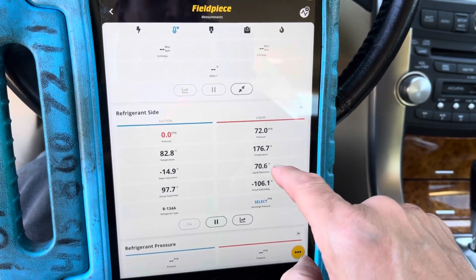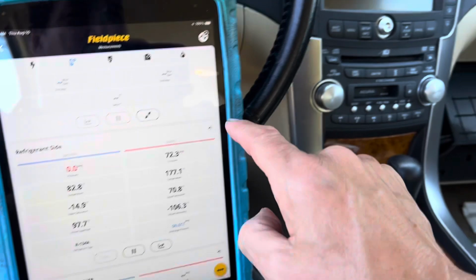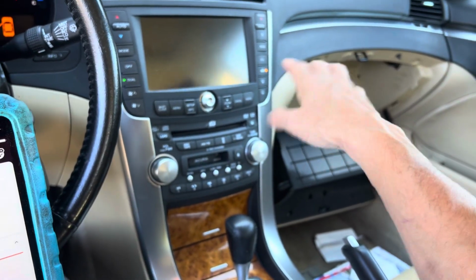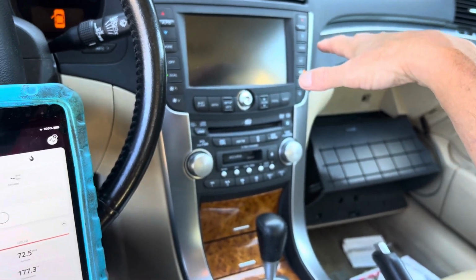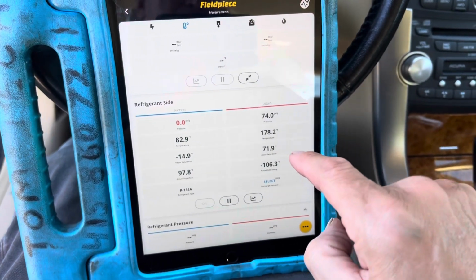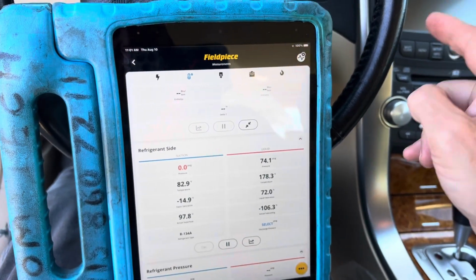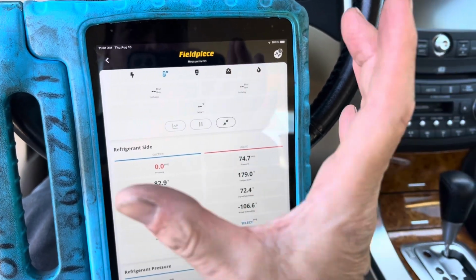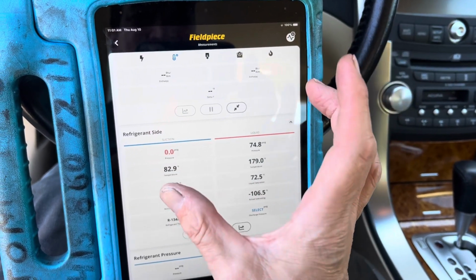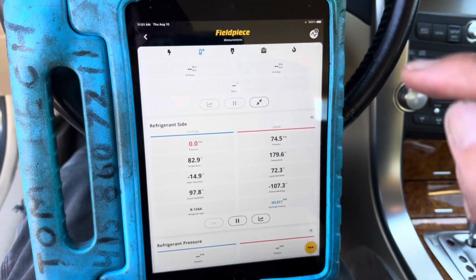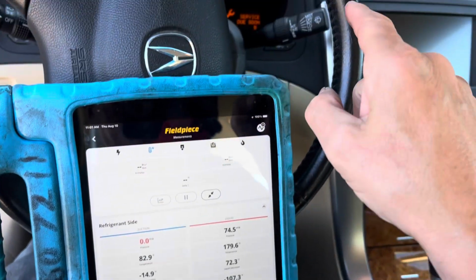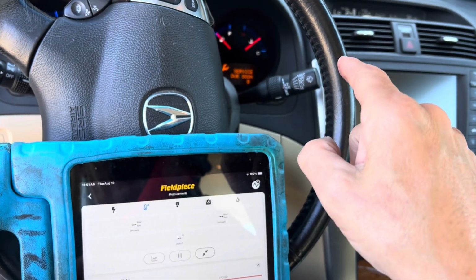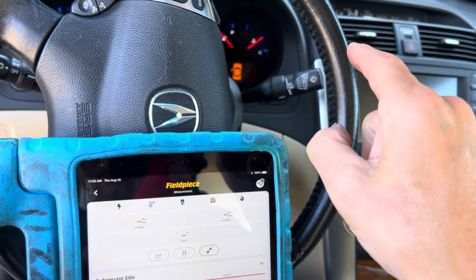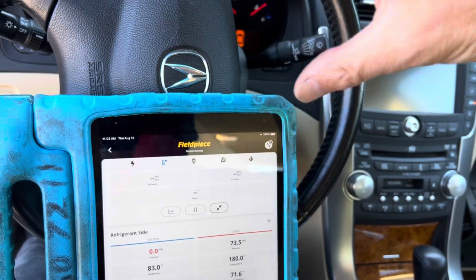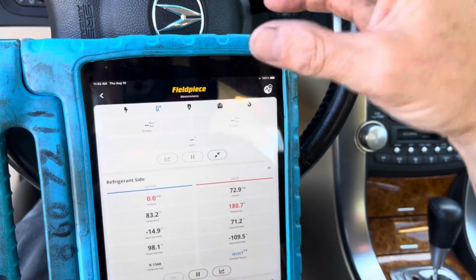All the oil is leaving the compressor and is getting trapped up in the evaporator and builds up in the evaporator. Then when this compressor burns out, a technician who doesn't read and doesn't know, or reads minimum and doesn't understand, because detailed instructions are not in compressors, goes to drain the oil out of this compressor, and it will show no oil. He'll pour it out and no oil will come out. Maybe 1 or 2 drops, that's it.